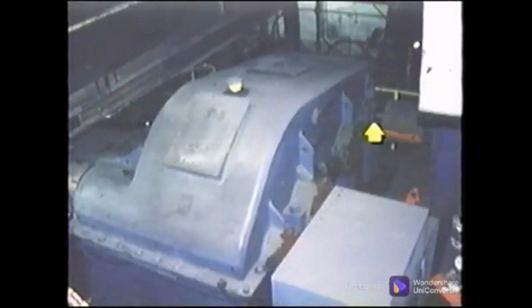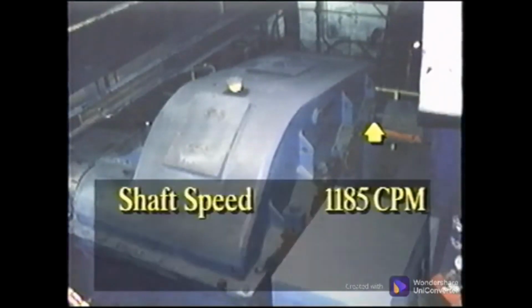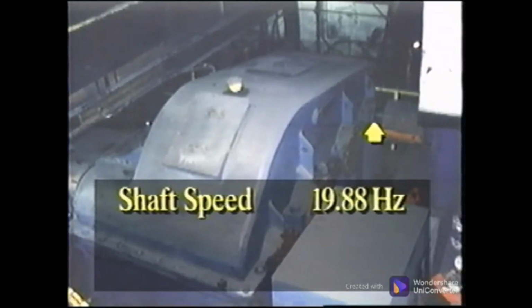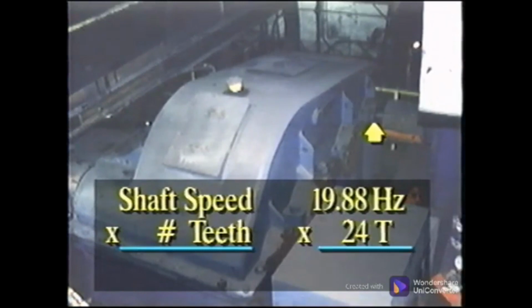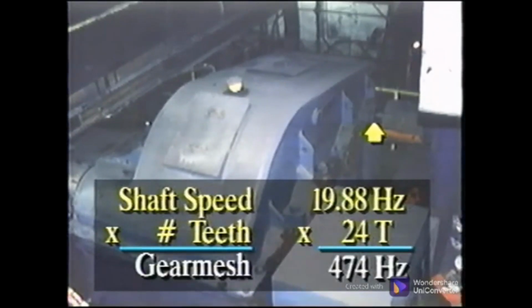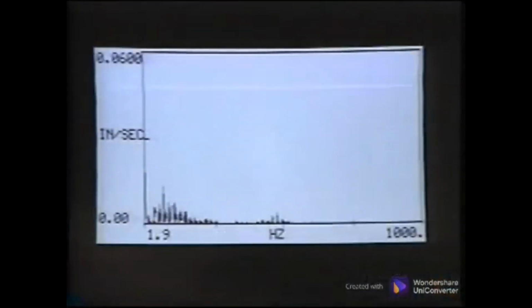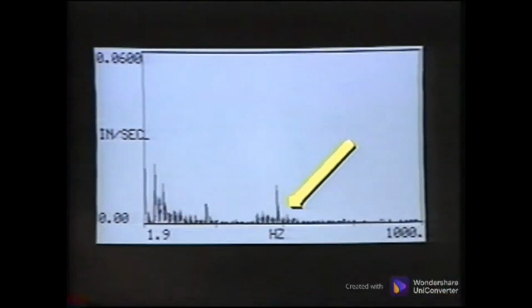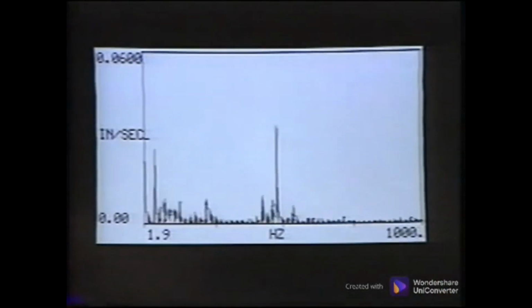The data we will view is from the input shaft, which has a speed of 1185 CPM, or about 19.88 Hertz. The gear has 24 teeth, so the gear mesh frequency is 474 Hertz. Watch the area around 474 Hertz closely. Notice that we can hear some variance in the sound as it is modulated.